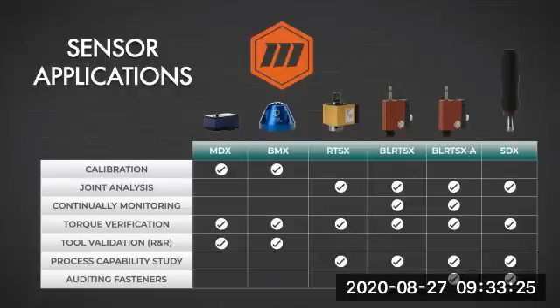Now, each sensor does have a specific range that it deals with, so you usually have basically 10% of the final or maximum output. You can see that with our gauge, that small little package, if we add too much torque to our sensor, we're going to damage that strain gauge.